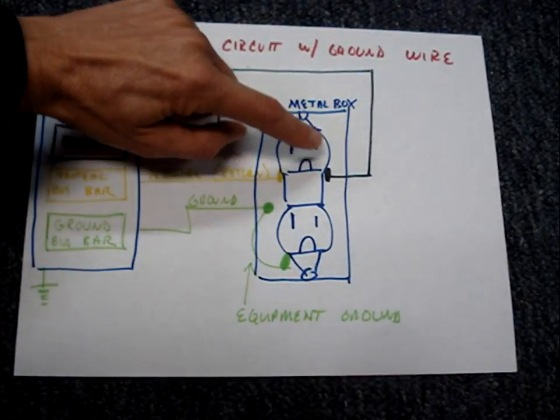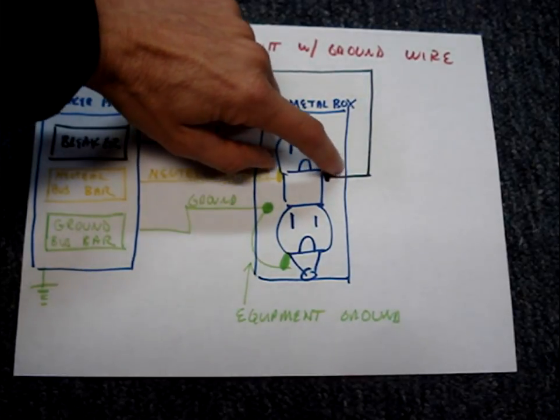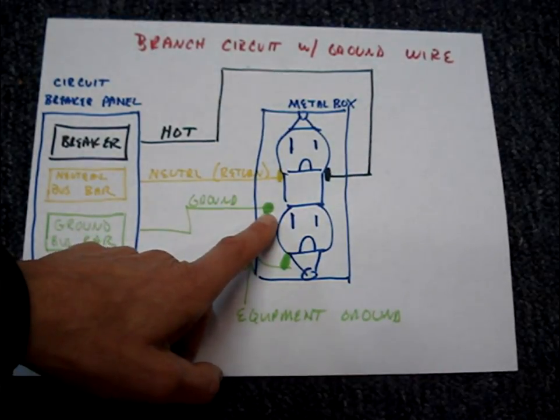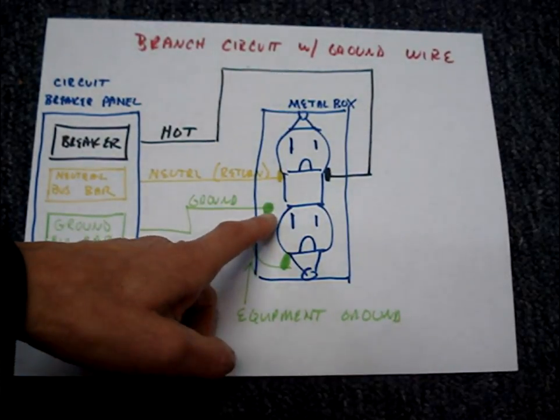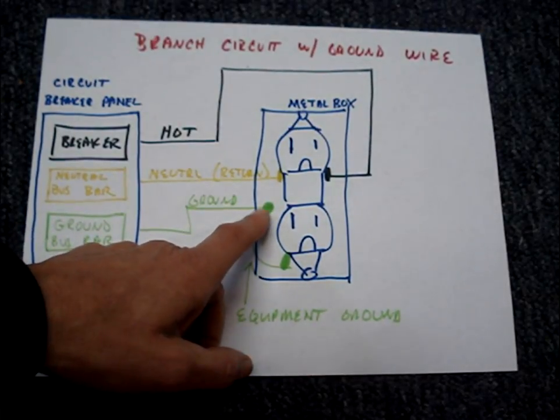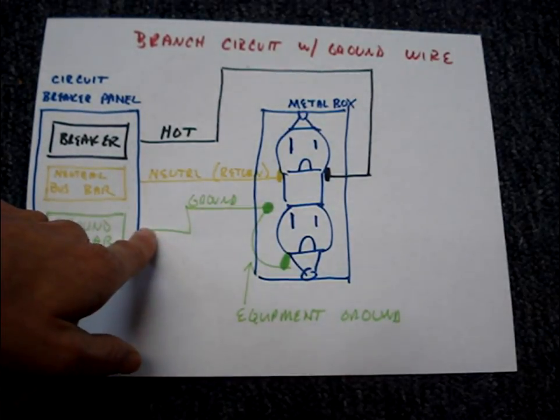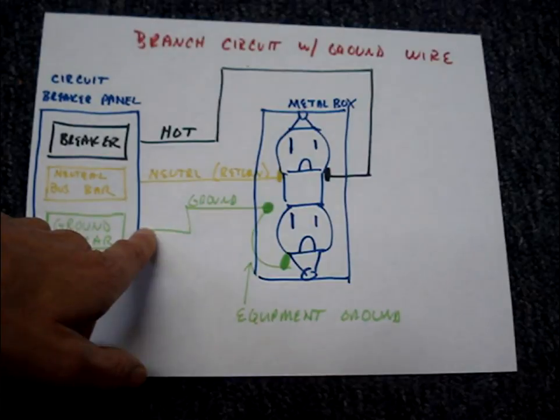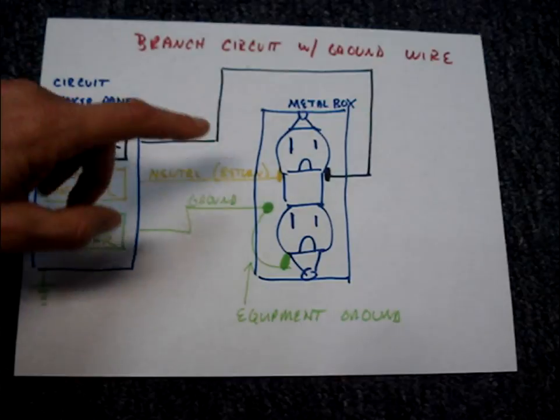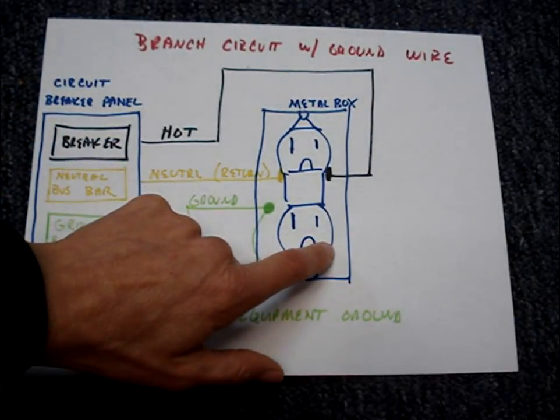It would create a direct short between the metal box and our lug that's holding on the ground wire, and the current would travel back to the breaker on this ground wire. There would be a high current situation that would trip the breaker and turn power off to the circuit and make the metal box safe to touch.